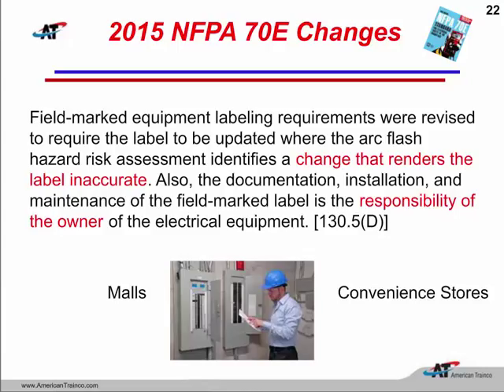Okay, now they give us an idea about that reviewing of that and who's responsible to put these labels on. So we'll take a look at that. These field-marked labeling requirements, they've revised these every year that a new 70E comes out. And so when we do the hazard risk assessment now, which is what it's going to be called, the arc flash hazard risk assessment, will not be called the analysis anymore. If it identifies that the label is inaccurate, they do want us to update the label, and it tells us who the responsibility of this field mark label is.